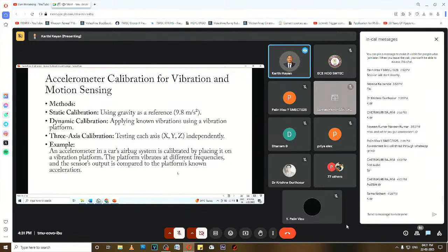Next, accelerometer calibration for vibration and motion sensing. Static calibration, dynamic calibration, and three-axis calibration are used. For static calibration, they use the reference value 9.8 meters per second squared, and dynamic calibration applies known vibrations using a vibration platform. Three-axis calibration means there are three directions, X, Y, Z. In each direction they will check the motion.